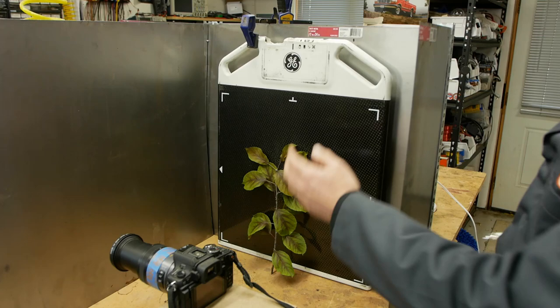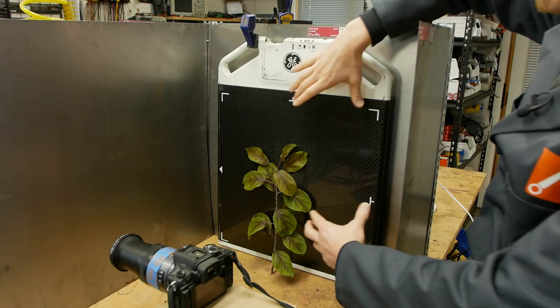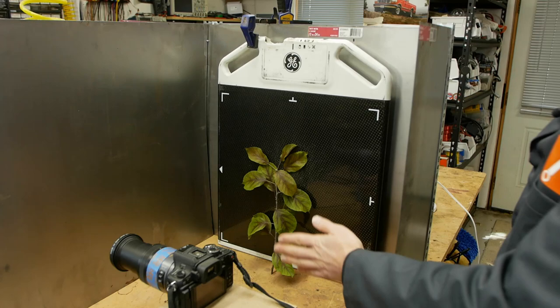And those photons come from a fluorescent screen that's also inside there. So when we get a shadowgram, when the X-rays come in and hit this, it actually produces light inside there when it hits the phosphor screen, and then the camera sensor is bonded right to that phosphor screen, so it's super sensitive. Another way you could build this is just to have a fluorescent screen and then a camera lens far away looking at the screen, but that wouldn't give you anywhere near the same amount of sensitivity just due to the area.